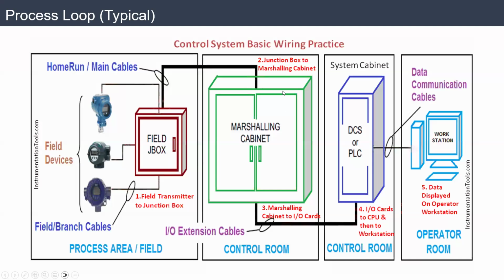Okay, what's marshalling? Marshalling is a collection for the cables only. It will take the cables from the field, it will enter this cabinet, and it's a matter of reorganizing these cables in the marshalling and again sending them back to the controller. Instead of sending directly from the field, it will sit in marshalling and just reorganize the cables, because you have many areas in the field with many cables. To organize them, it will be organized in the marshalling cabinet. Thanks, Ala, for your question. Okay, any other questions before we move to the next?